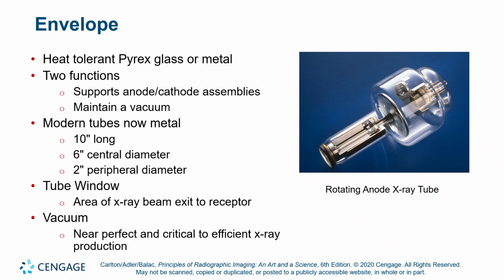Vacuum: near perfect and critical to efficient X-ray production. Okay, so you can have inefficient X-ray production with a very low pressure X-ray tube. Remember, the Crookes tube was a low pressure system rather than a perfect vacuum system. But in modern engineering, we can effectively create a perfect vacuum X-ray tube. Okay? But that means as soon as that vacuum is violated, as soon as the envelope is compromised, the X-ray tube is immediately gassy and worthless. Okay? And that is the number one cause of tube failure, a gassy X-ray tube by arcing.